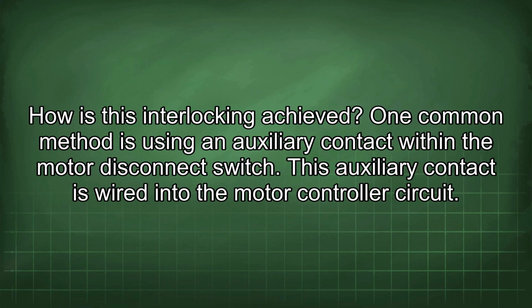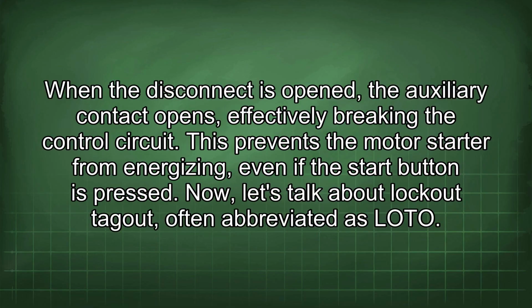One common method is using an auxiliary contact within the motor disconnect switch. This auxiliary contact is wired into the motor controller circuit. When the disconnect is opened, the auxiliary contact opens, effectively breaking the control circuit. This prevents the motor starter from energizing, even if the start button is pressed.